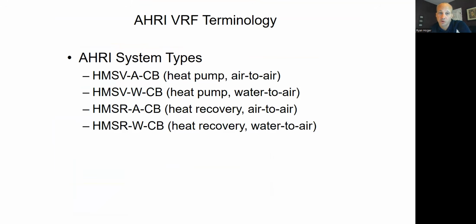For VRF, there's 4 kinds of systems that are included there. There are the heat pump systems, which means it either heats or cools at any given moment in time, not both simultaneously. And there's heat recovery, which means it can push heat from one zone to the other and run heating and cooling simultaneously. And then for each of those, there's air to air, meaning it takes heat from the air and puts it to the indoors. And there's water to air, which means it takes heat from a water loop and puts it to the indoors, meaning somewhere you have a cooling tower and boiler plant that it attaches to.